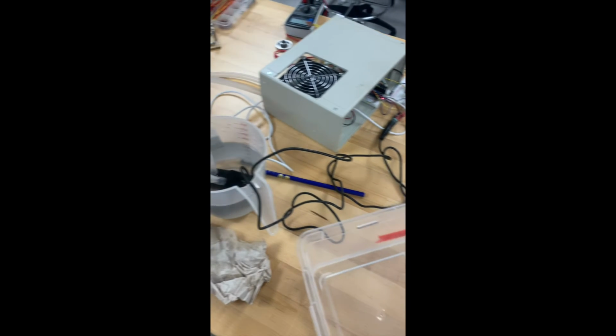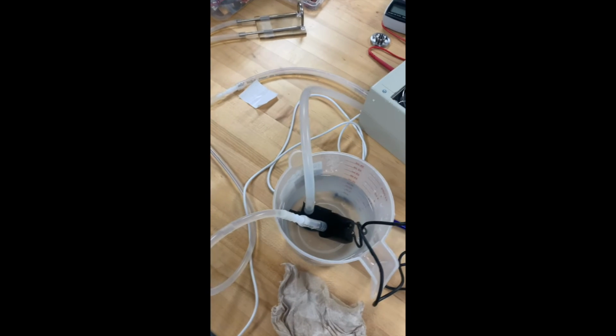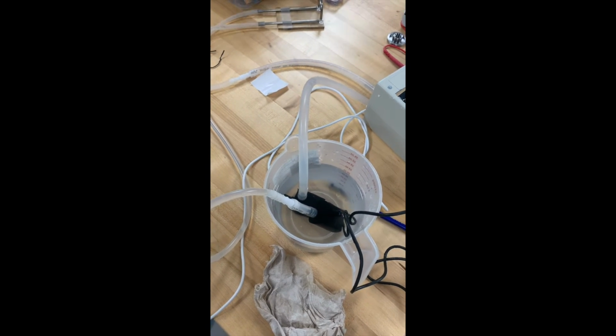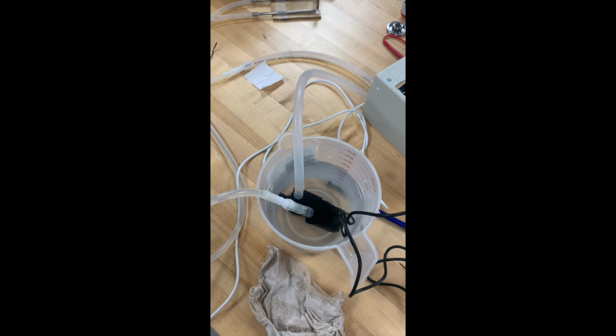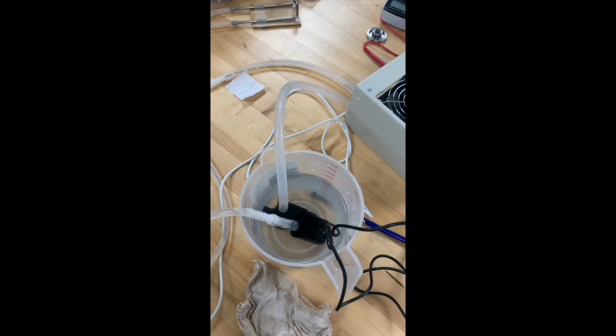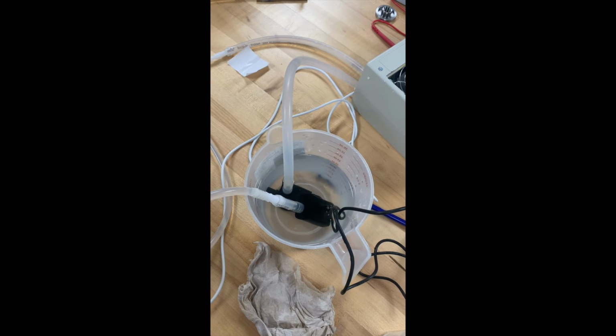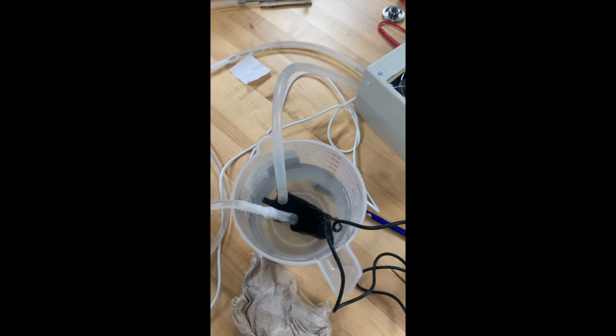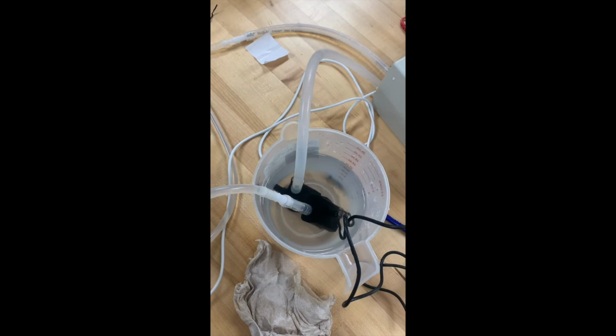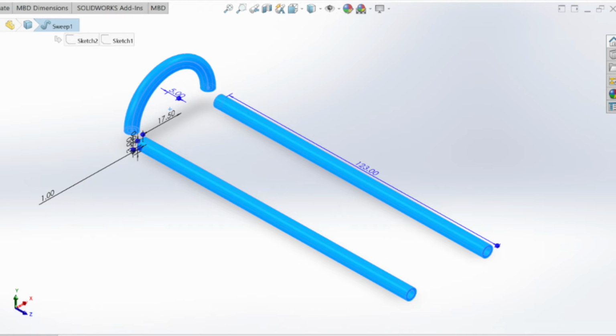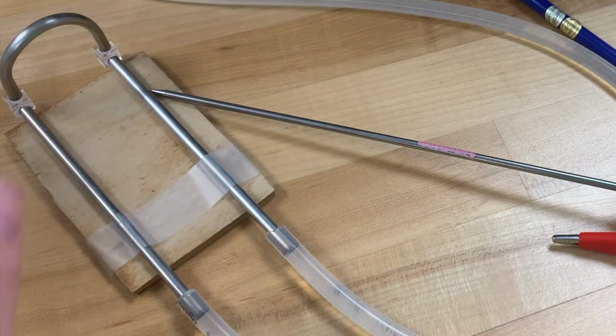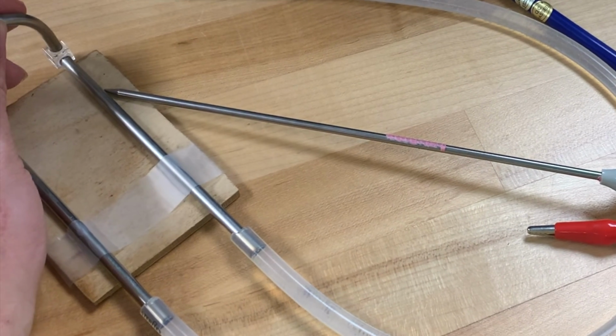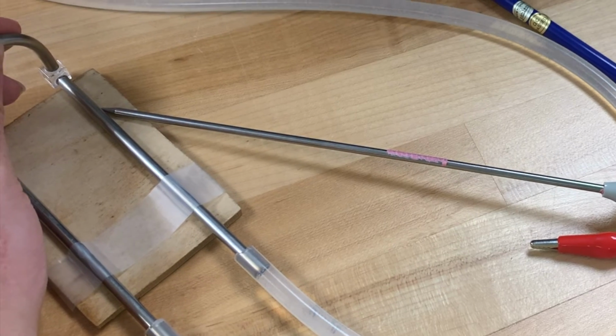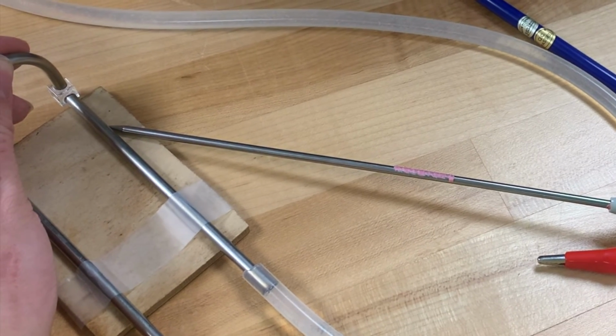One thing we are proud of is our water cooling system. We had to conceptualize a way to deliver a cold stimulus to the patient's cervix, and we went through several ideas until we decided on water cooling. Creating a working circuit of tubes, pumps, and reservoirs was quite difficult and required some trial and error to get the water circulating and the water cooled. In addition, we had to fabricate a custom probe that water could travel through. The design and fabrication of the probe required a lot of technical as well as anatomical knowledge.